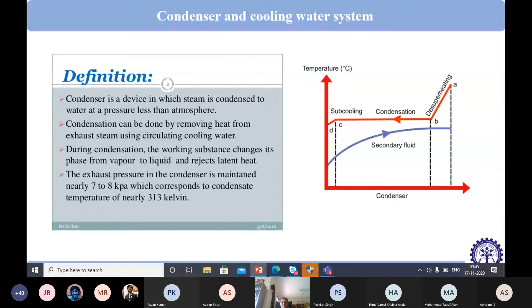So with all these things, let us go to what the different types of condensers are. Two main categories of steam condensers are direct and indirect contact condensers. Indirect contact condensers, particularly steam condensers, are also called surface condensers, because here the condensation takes place on the surface of the coolant tube. For large power plants, direct contact condenser. What is a direct contact condenser? Water and steam are made to come in contact directly, and that is a direct contact condenser. In a large power plant, the main condenser, that means the exhaust steam from the turbine, is condensed in surface condensers. Feed water heaters and deaerators are also condensers. This I have told already. And a feed water heater could be of direct or indirect contact type, while deaerators are direct contact condensers.